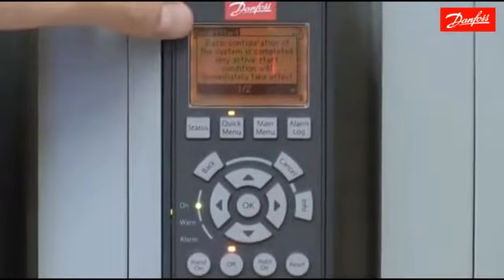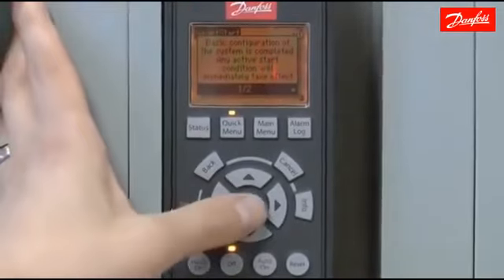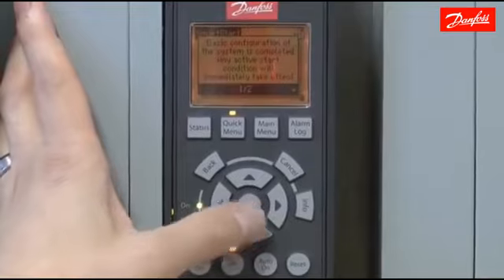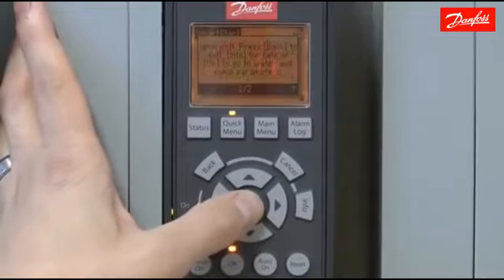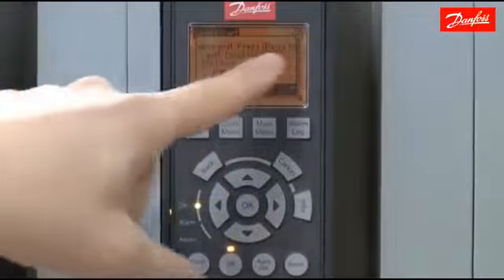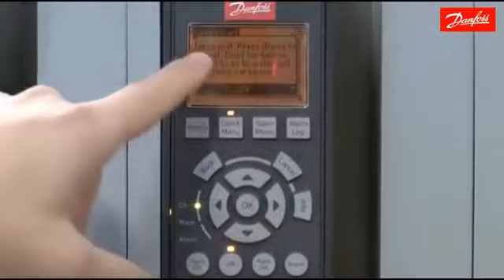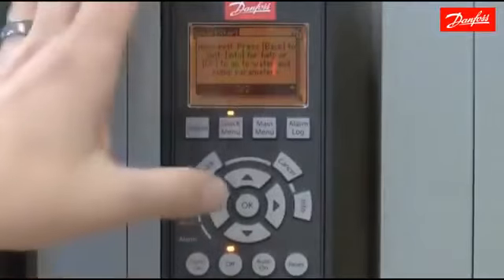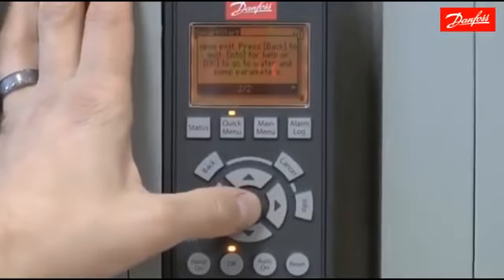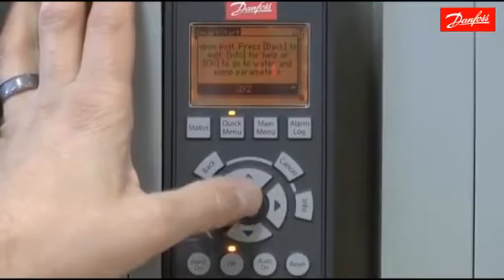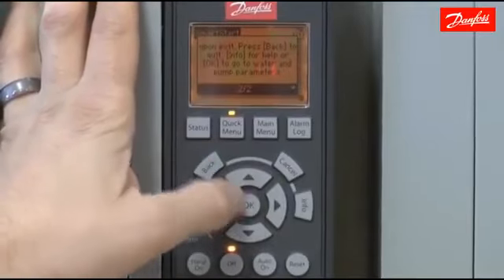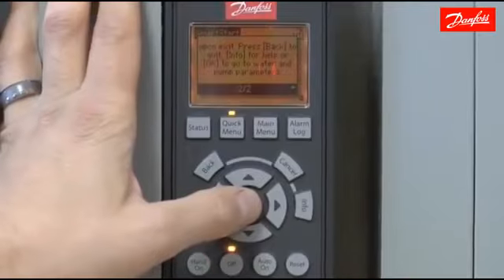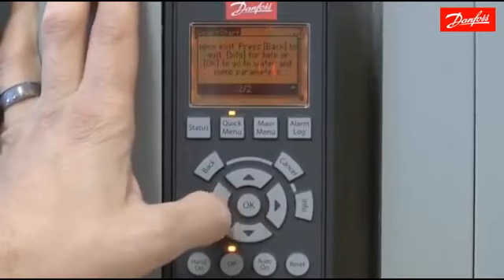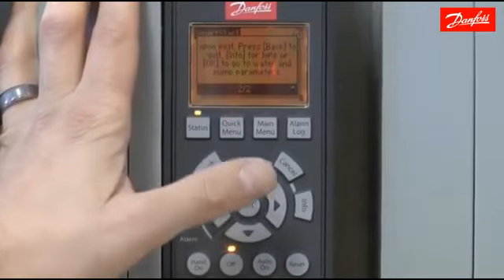This message here is telling me now the basic configuration of the startup is complete. So at this point, any start command condition will take effect and start the drive. Press OK. At this point, I can press back to quit or OK to go onto the water pump parameters. There are further sets of menus that can be used for the advanced water application features. For this tutorial, we're not going to go into those, so I'm going to press the back key.